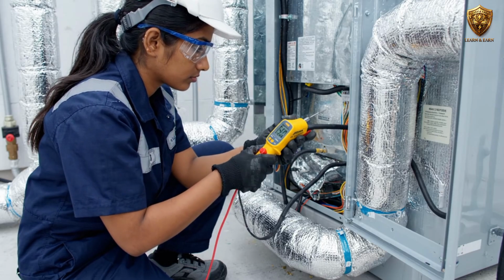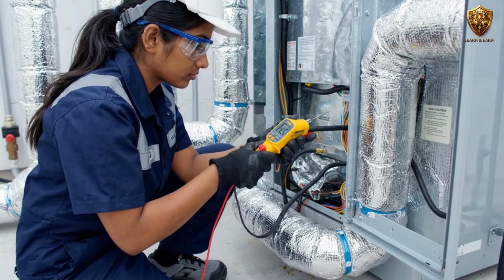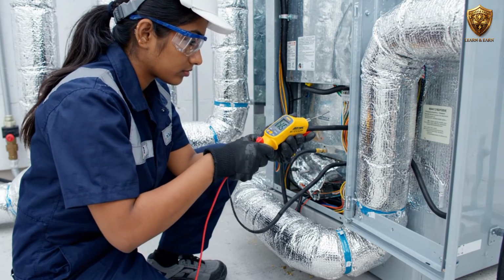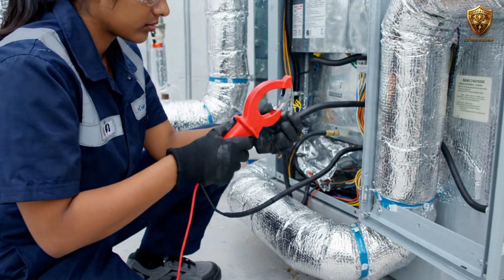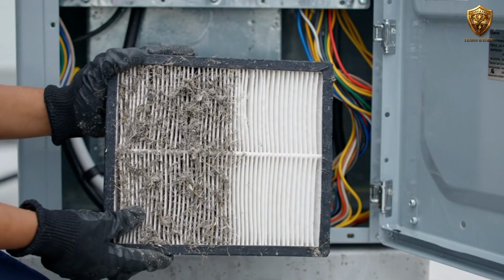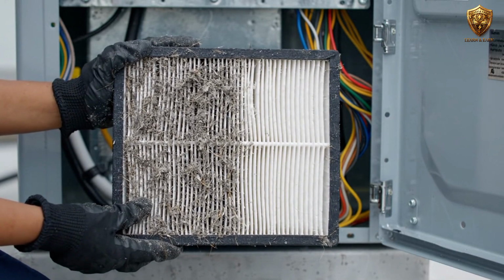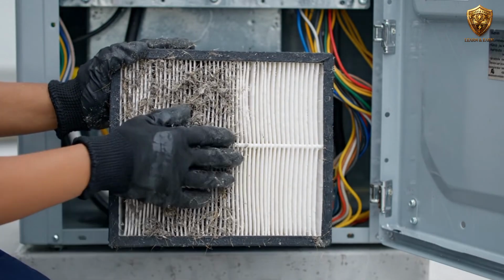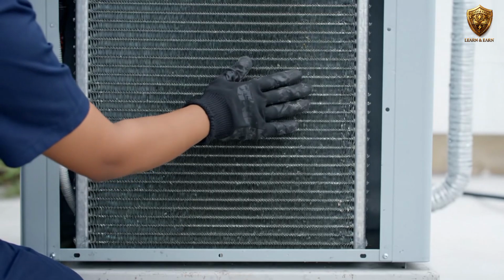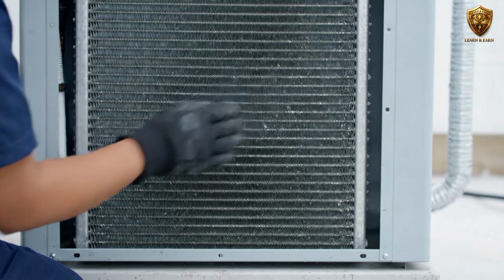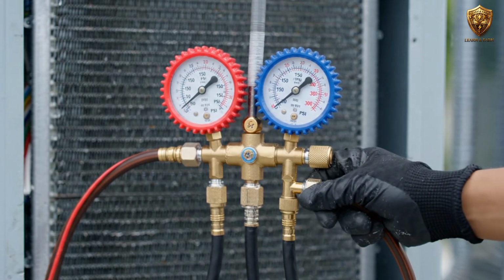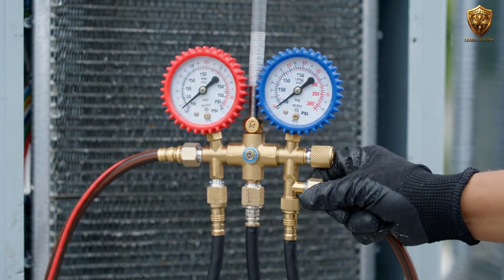If the indoor airflow is weak, stay focused on the air side until you have enough evidence to move on. If the indoor blower is normal but the outdoor unit is silent, investigate power, controls, contactor operation, and outdoor components. If the outdoor unit runs but cooling is poor, evaluate airflow, condenser condition, temperatures, and refrigeration performance.